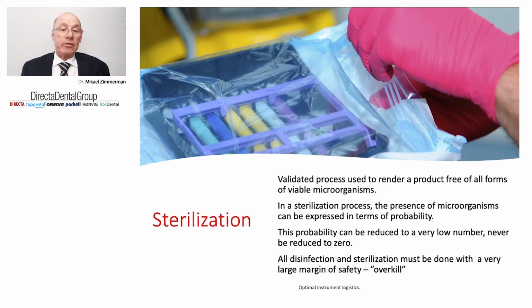The problem with the sterilization process is that the presence of microorganisms can only be expressed in terms of probability. So all disinfection and sterilization processes must be done with a very large margin of safety, something that we call an overkill, to be sure. So there is a measurement, sterility assurance level, that is interpreted as: in 1 million sterilized instruments, there must not be more than one viable microorganism, which is actually a theoretical measurement.